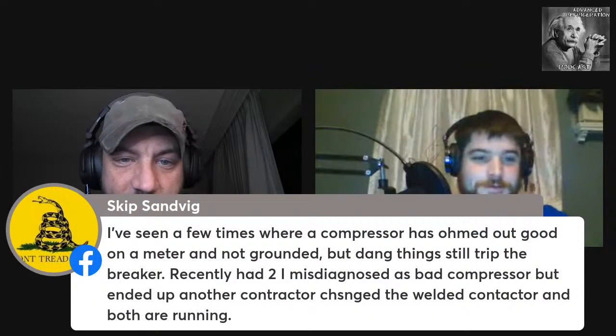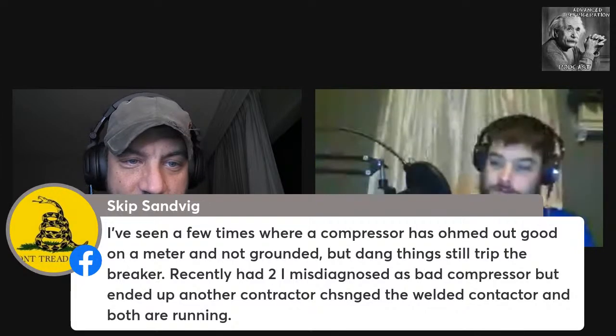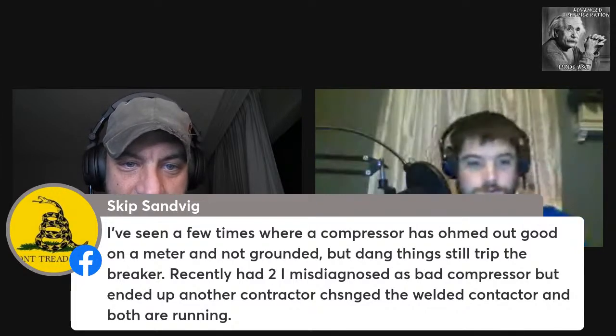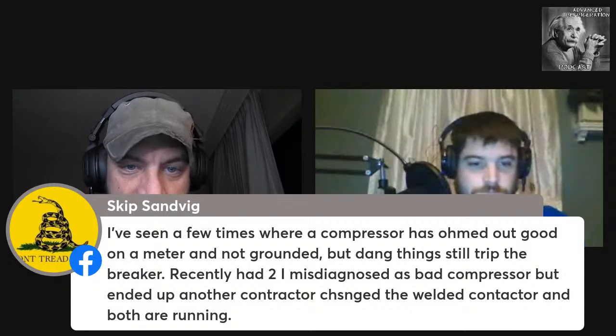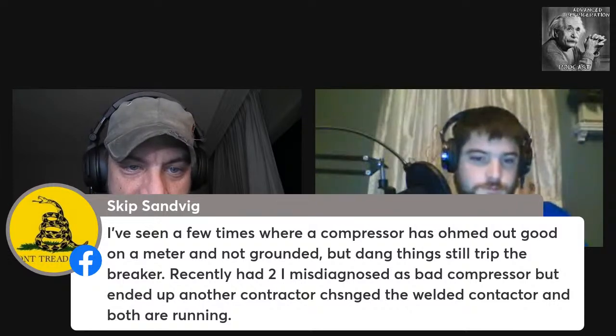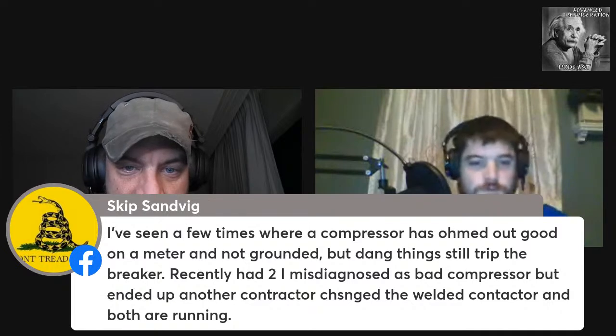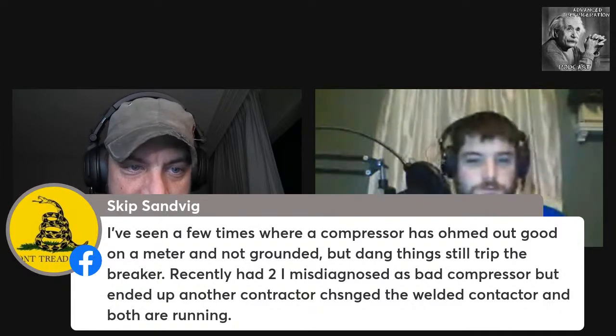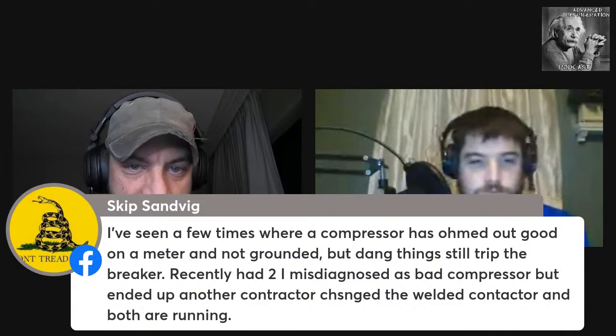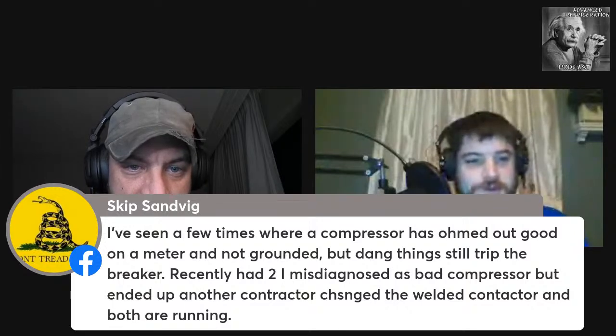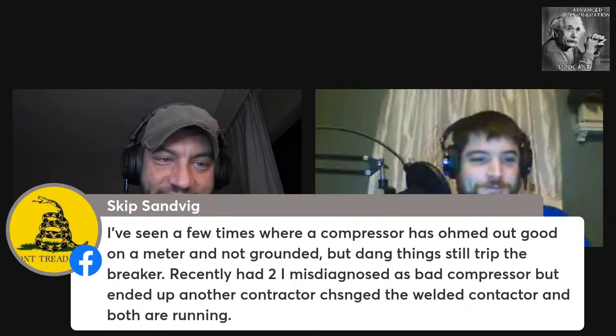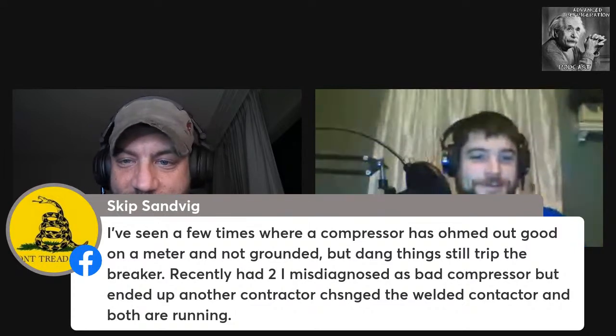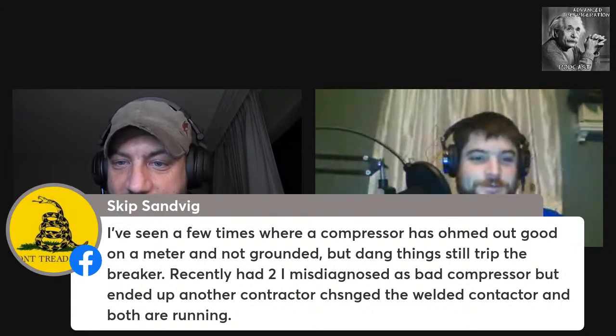I've seen a few times where a compressor is ohmed out on a meter and not grounded, but the dang thing still trips the breaker. Recently had two I misdiagnosed as bad compressors. Ended up another contractor changed a welded contactor, and both are running. Yeah, it's a real kick in the dick there. Come on, we've all had it. We've all had that happen once or twice.